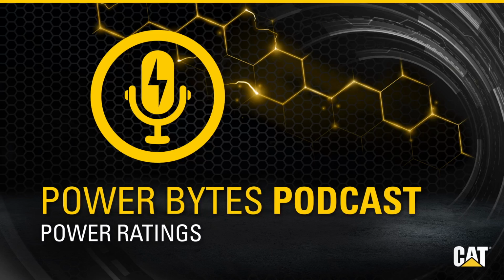Thanks, Brian, for taking us through that. So it really seems like you must start with the user expectations of load and runtime and then move to the ratings to assure the expectations are met. Is that correct? Absolutely. So the ratings are intended to help our users understand how much power they can get out of the generator set and for how long. It's really an agreement between the manufacturer and the user as to what the maintenance intervals are and how to maintain and get the most life out of their product.